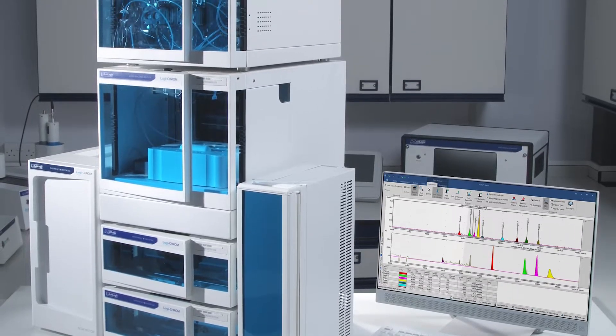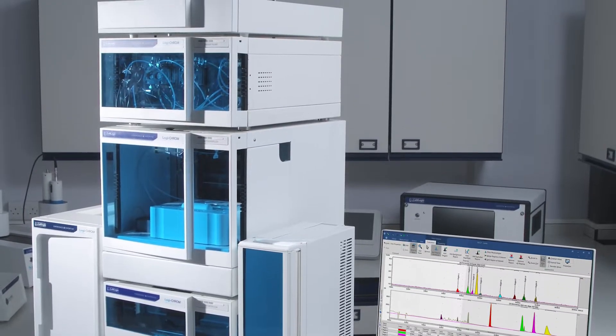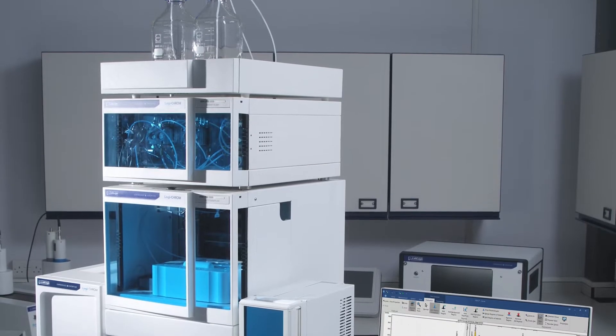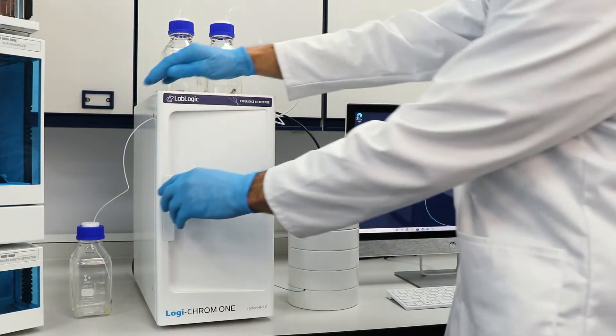Until now, radiopharmacies have traditionally had to buy modular HPLC systems. With bench space being a premium in these environments, we have developed the Logichrom One, which combines the most common HPLC modules into one compact system.